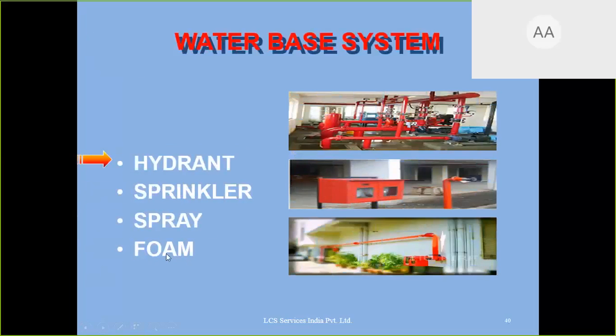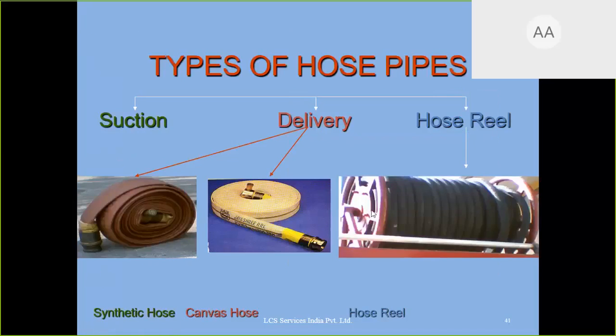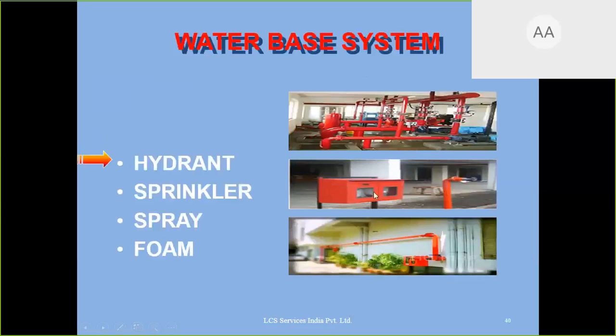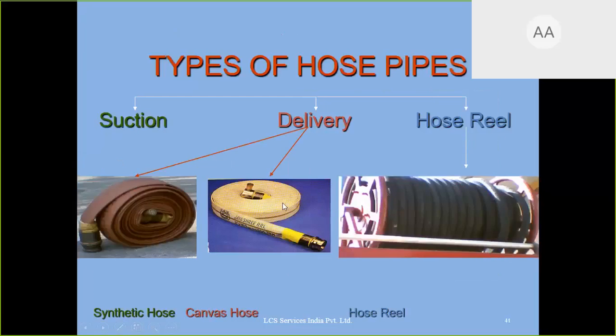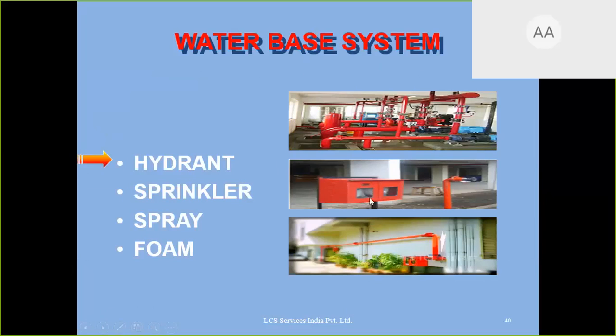Now what is the hydrant system? Suction pipe, delivery pipe, hose pipe, right? So in this hose box, you will have two white color delivery hose pipes. Each has 15 meter length, so in total you have 30 meter, and you will get this point after every 30 meter in the plant. As per NBC guideline, hose box and hydrant point have to be installed after every 30 meter.